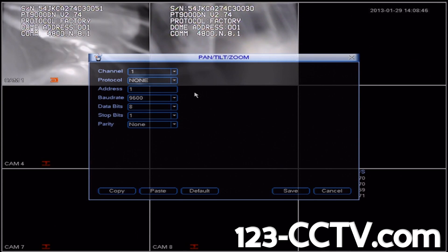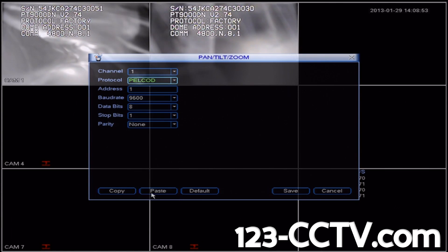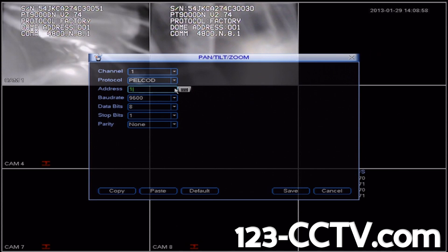I've looked up the settings ahead of time, and I know that the correct protocol for this camera is Pelco D. So we'll scroll down and click Pelco D. The address for the camera by default is going to be address number 1. Since we're only configuring one PTZ for now, we'll leave the address as 1.